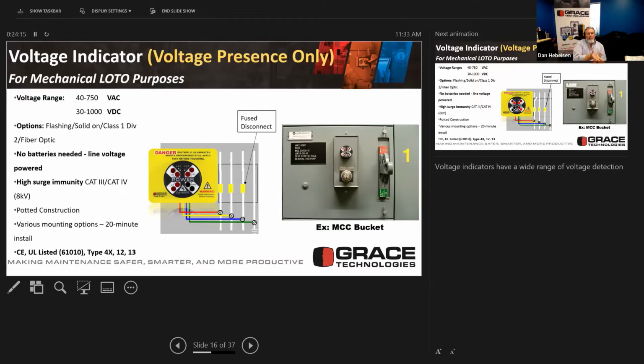So it gives you that opportunity to see the visual, and then it also will verify that those three locations are actually, the voltage levels are similar. And if that disparity between A to B or B to C gets to around 11%, it's going to start to flash on the ground. So a lot of customers like this when they have to do some troubleshooting as a problem occurs.